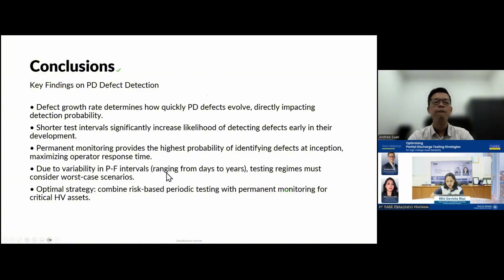Second, fourth point: due to the different variety in the P-F interval, ranging from days to years, we won't know for sure. As I mentioned, a surface discharge can fail your termination within weeks or days, while internal discharge - maybe a current CT with a void in the insulation - may take years to fail. You won't know. So you need to know what type of asset you're dealing with, then plan your testing regime.